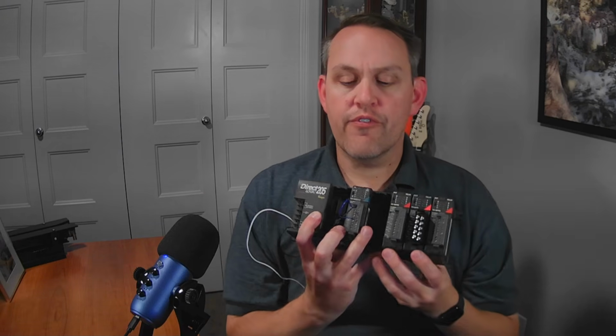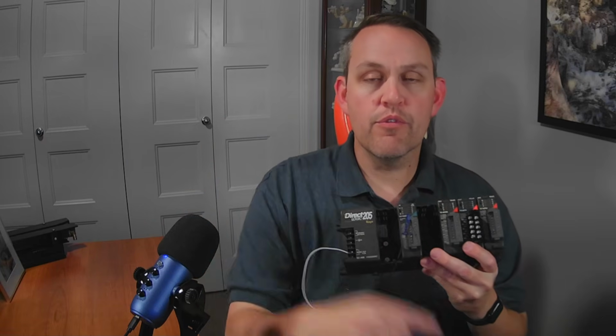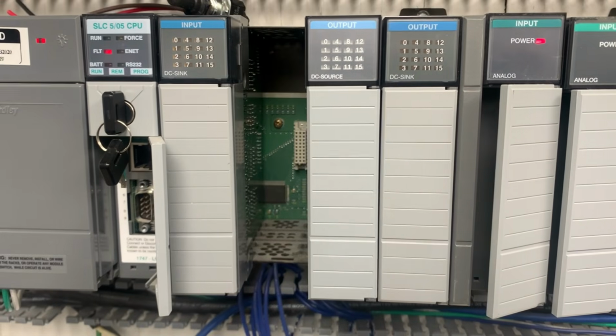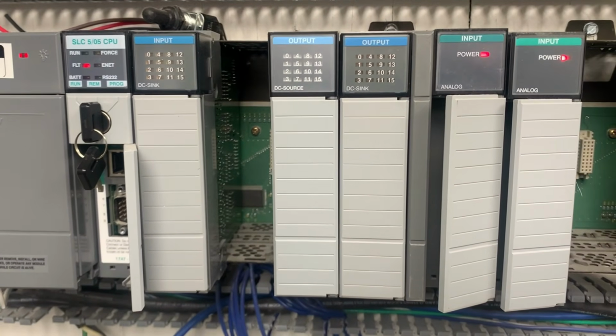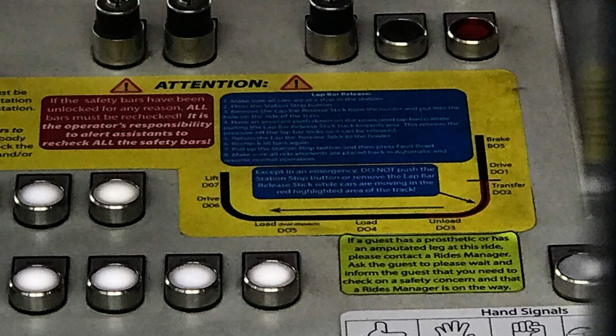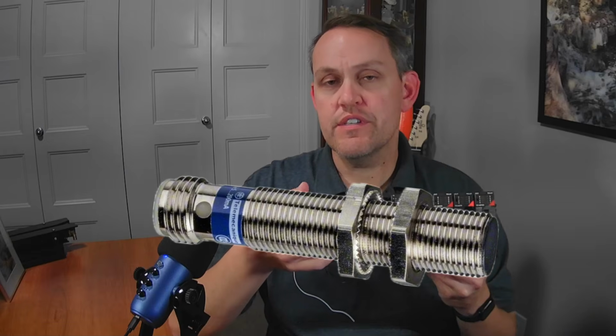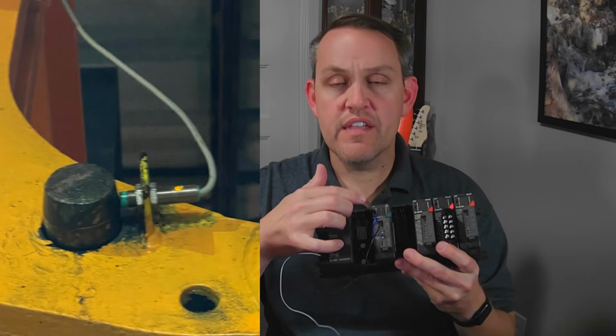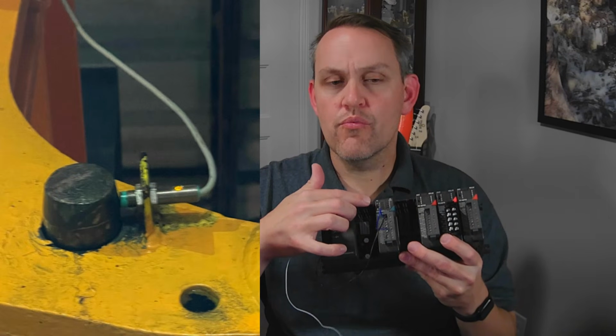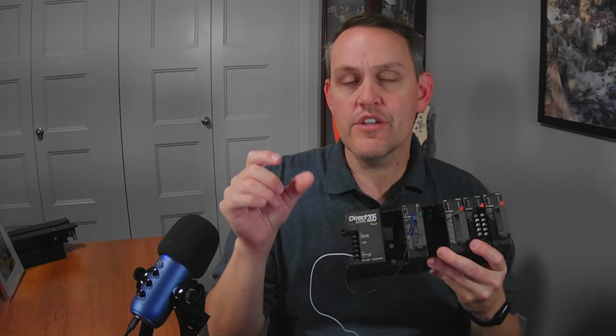All right, the first step of the scan reads the inputs. The scan comes down through the processor and reads the inputs and starts to make note of all of the real world inputs that are turned on. Remember, these are coming from real world devices like push buttons and proximity sensors and things like that. The scan takes that information and writes it in special slots inside the logic, and that puts it inside the logic code. So next, the scan solves the logic.